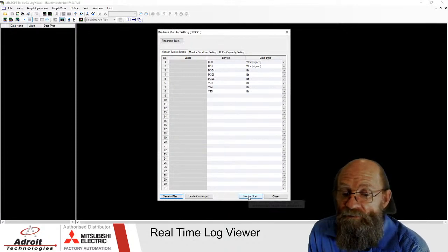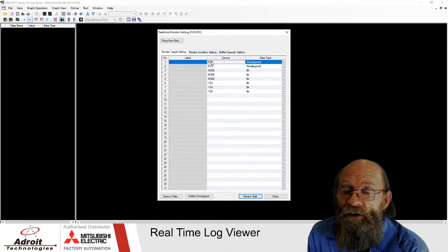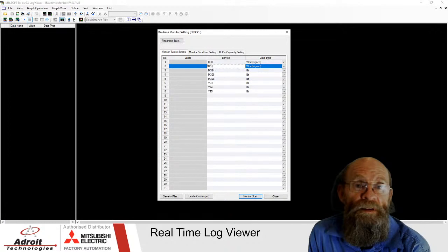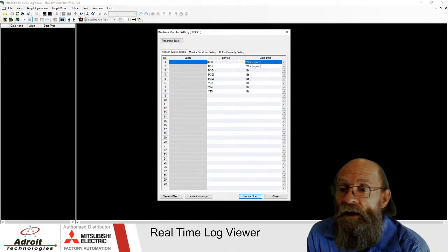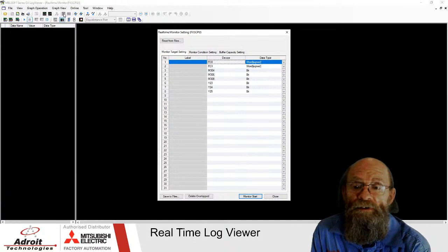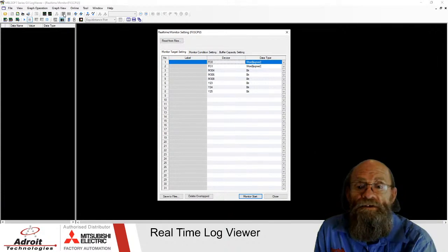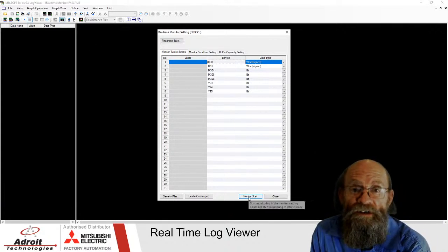And all you need to do is just push the start monitor button, and you're on the go. There's a couple of buttons on top here that you need to be aware of. When you're monitoring analogs like I'm going to do here now, analog values or words, double words, maybe you want to monitor your high-speed counter or any variables like that, these buttons here will reformat your chart, because it will just stay stationary in one position all the time until you expand the chart to see the data on the chart. And we'll see that just now happen.